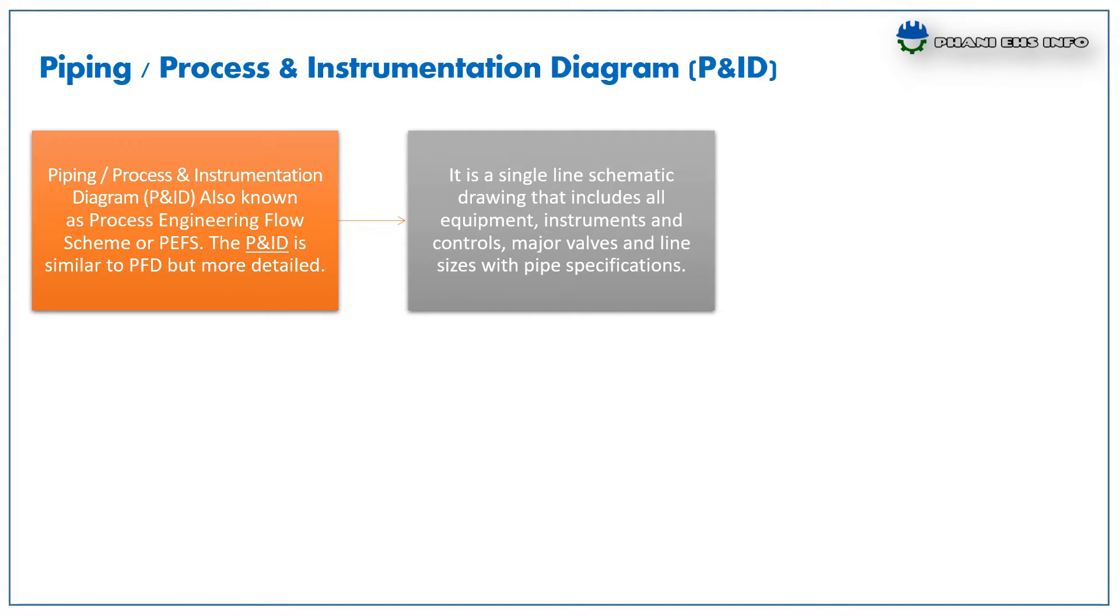It is a single line schematic drawing that includes all equipments, instruments and controls, major valves and line sizes with pipe specifications. It is the first important document that controls the activity of all related engineering groups.